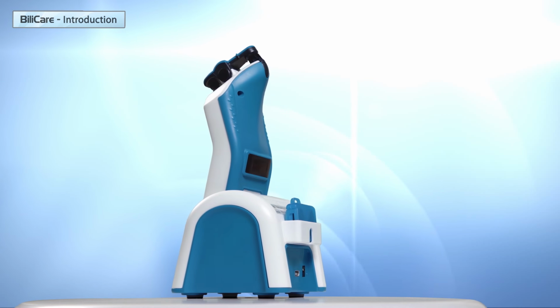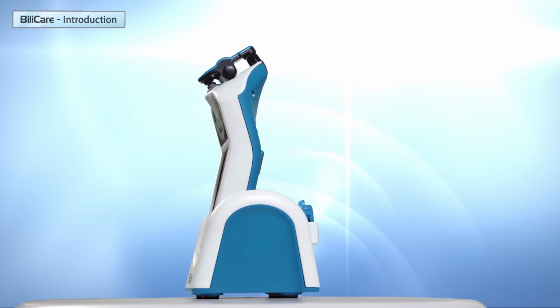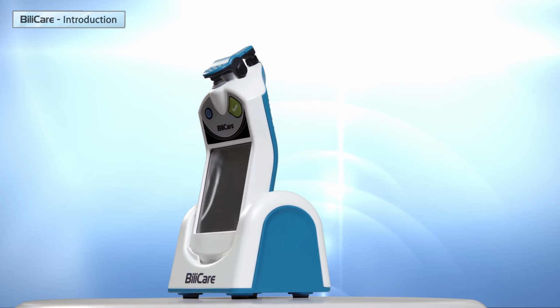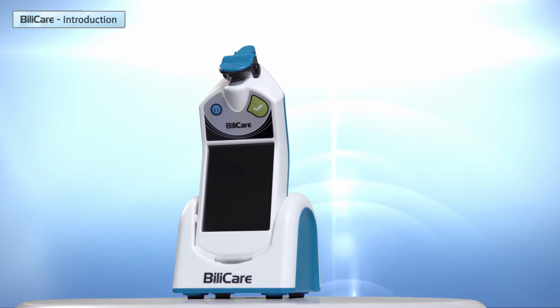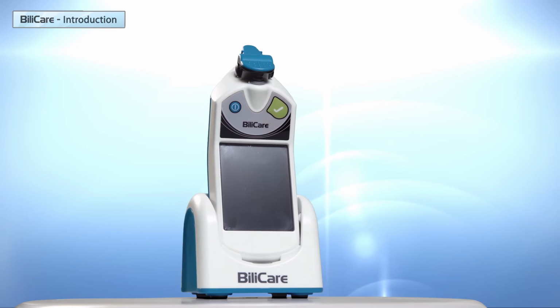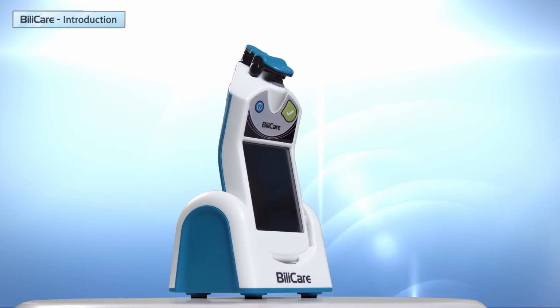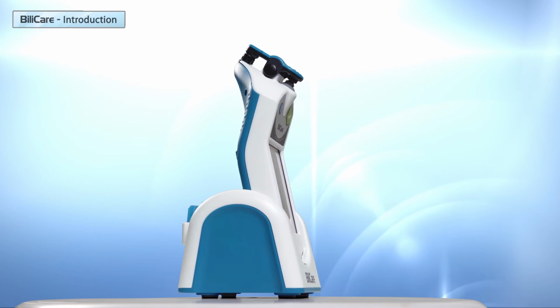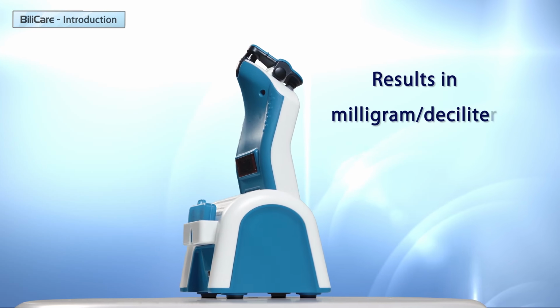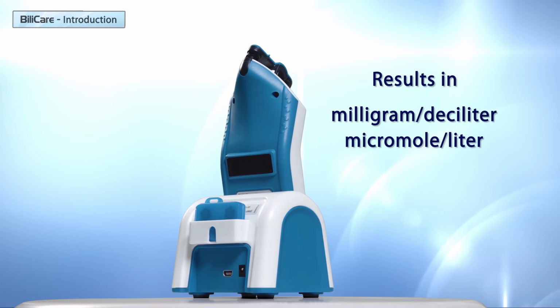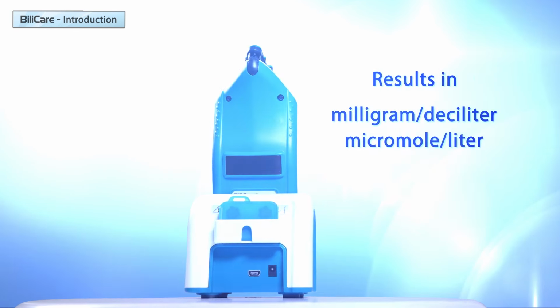BiliCare is a non-invasive transcutaneous bilirubin meter for neonates. It is a screening device that helps caregivers decide whether a neonate should undergo an invasive blood test for bilirubin measurement. The results may be displayed in milligram per deciliter or in micromole per liter units.